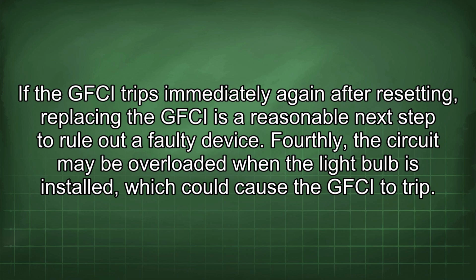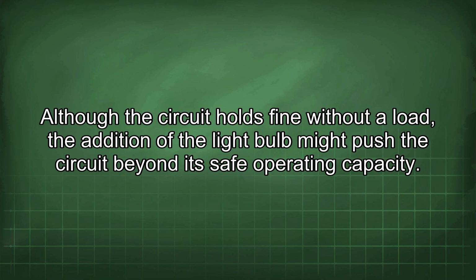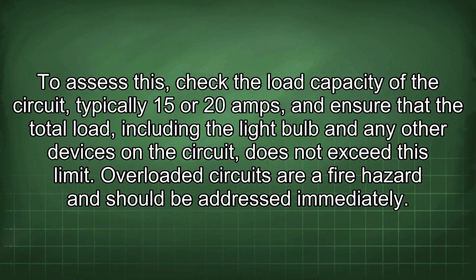faulty device. Fourthly, the circuit may be overloaded when the light bulb is installed, which could cause the GFCI to trip. Although the circuit holds fine without a load, the addition of the light bulb might push the circuit beyond its safe operating capacity. To assess this, check the load capacity of the circuit, typically 15 or 20 amps, and ensure that the total load, including the light bulb and any other devices in the circuit, does not exceed this limit. Overloaded circuits are a fire hazard and should be addressed immediately.